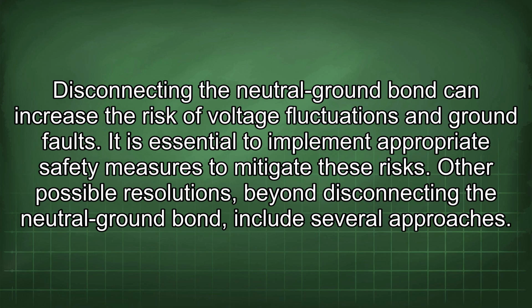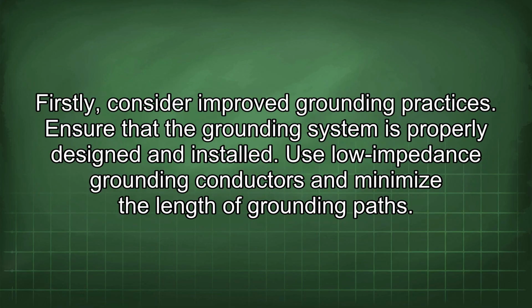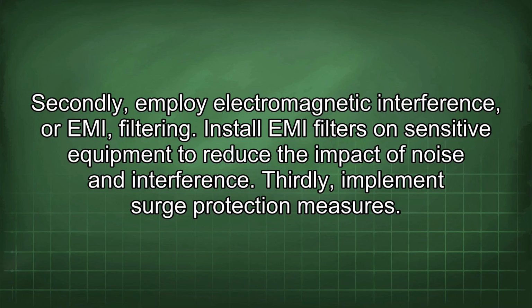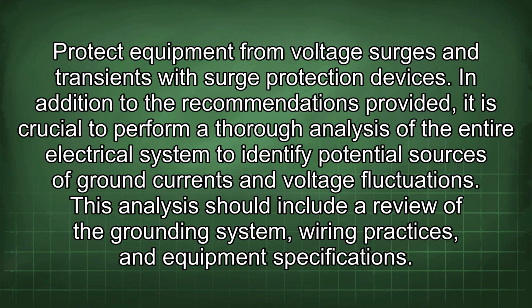Other possible resolutions beyond disconnecting the neutral ground bond include several approaches. Firstly, consider improved grounding practices. Ensure that the grounding system is properly designed and installed. Use low impedance grounding conductors and minimize the length of grounding paths. Secondly, employ electromagnetic interference or EMI filtering. Install EMI filters on sensitive equipment to reduce the impact of noise and interference. Thirdly, implement surge protection measures. Protect equipment from voltage surges and transients with surge protection devices.